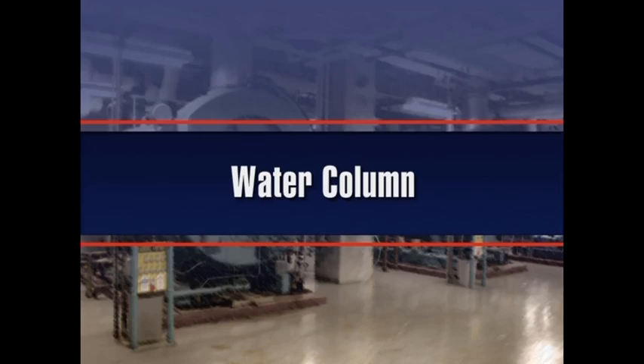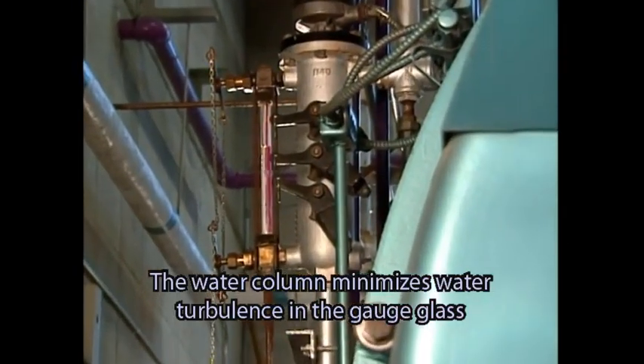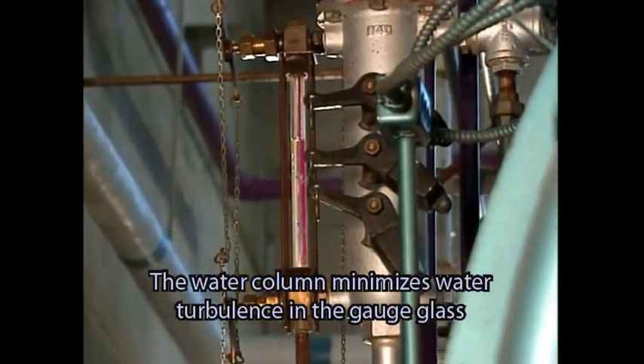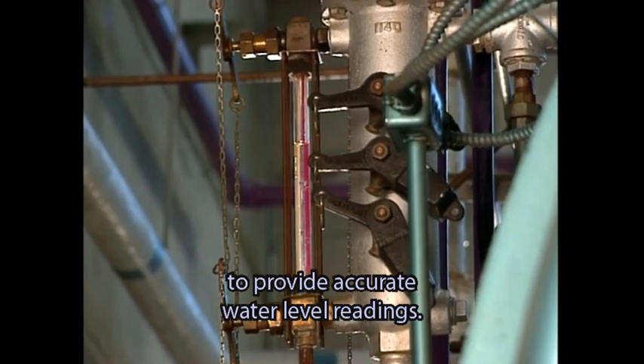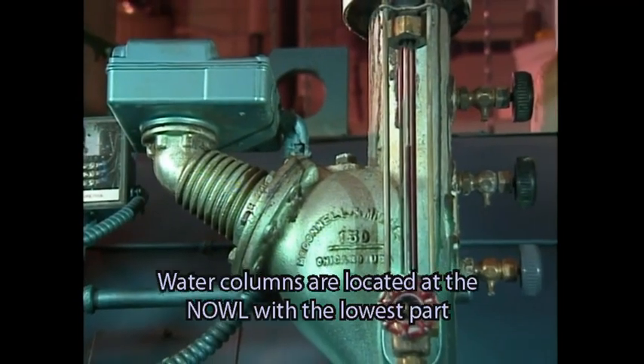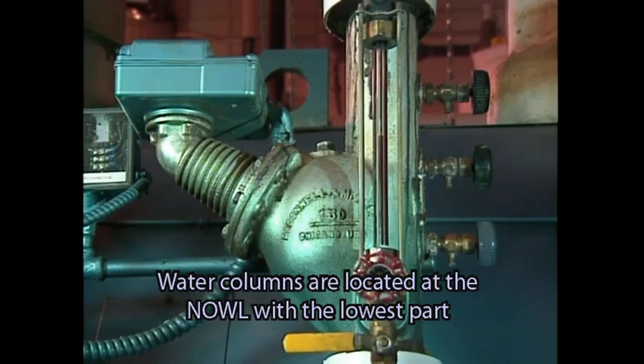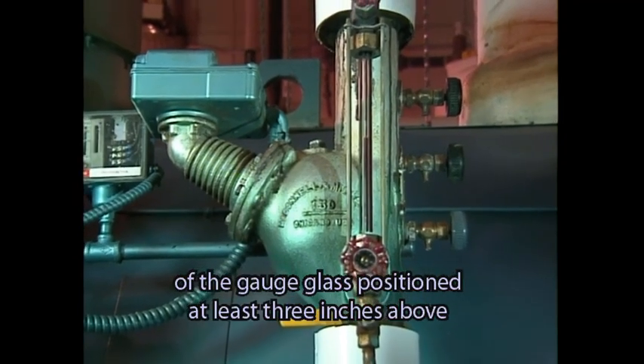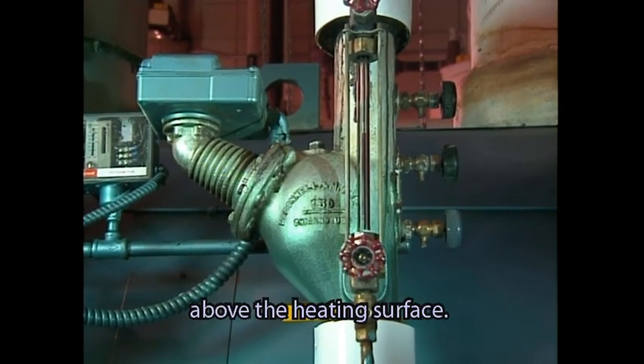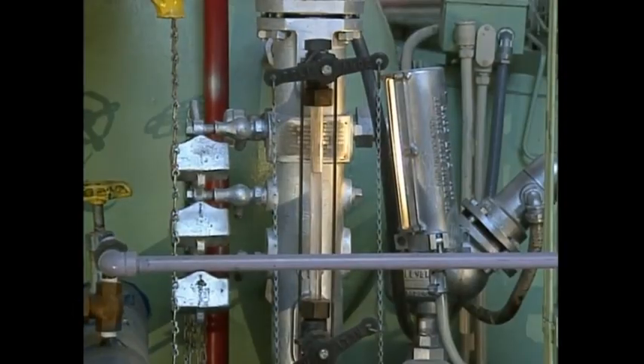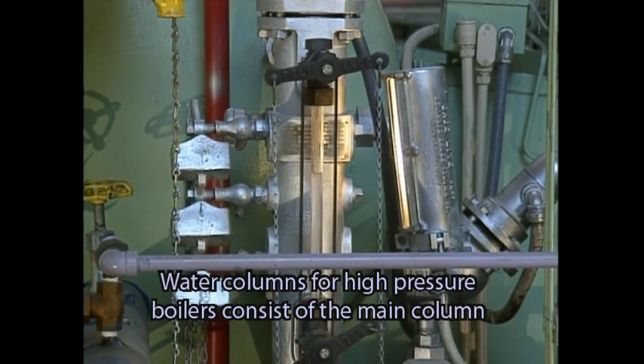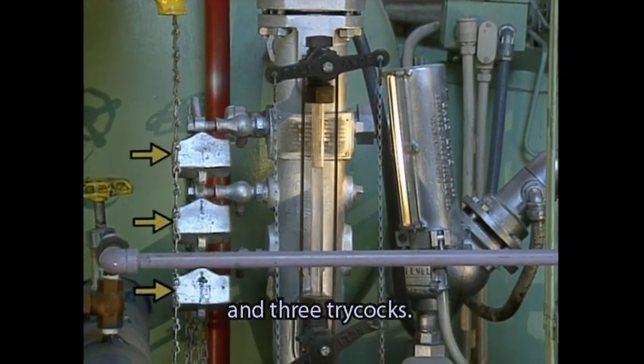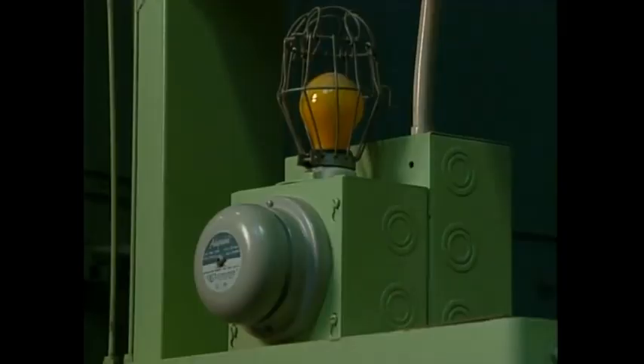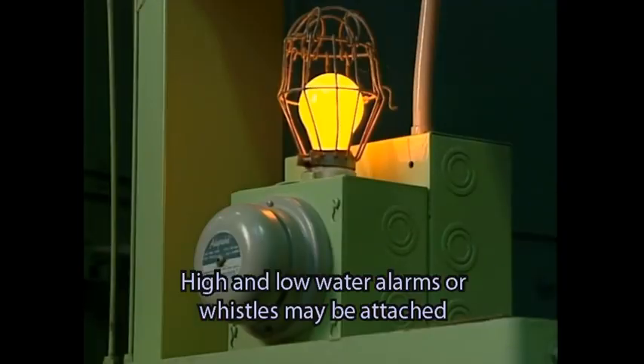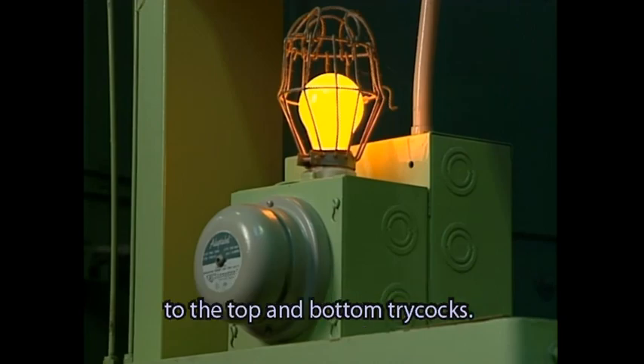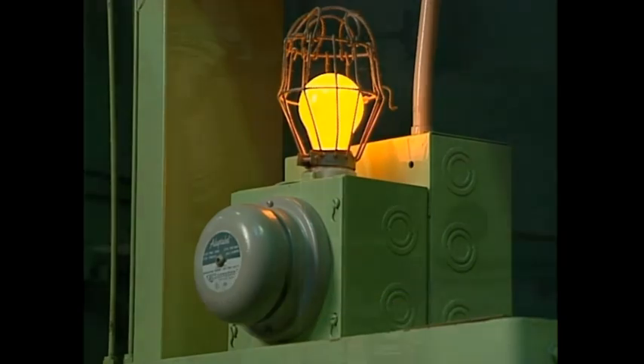Water column. The water column minimizes water turbulence in the gauge glass to provide accurate water level readings. Water columns are located at the NOWL, with the lowest part of the gauge glass positioned at least 3 inches above the heating surface. Water columns for high-pressure boilers consist of the main column and 3 try-cocks. High and low water alarms or whistles may be attached to the top and bottom try-cocks.